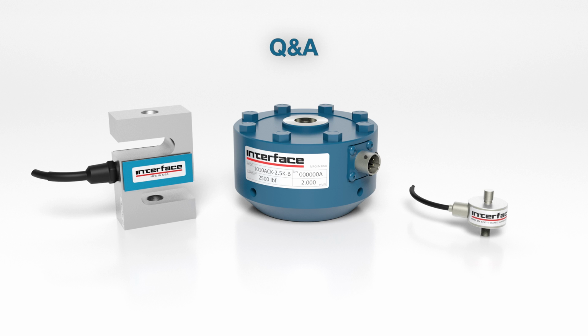Can you explain a little bit more about the grounding loop? Well, the goal is to just keep the ground only on one side of the sensor. If you ground on the load cell body, oftentimes you've now created an opportunity for noise to be introduced into the system. There are very rare situations where it can actually help reduce noise or provide better grounding. Again, it's going to depend on the application and where the potential sources are coming from and what those sources are. Probably best reviewed on an application-specific basis.